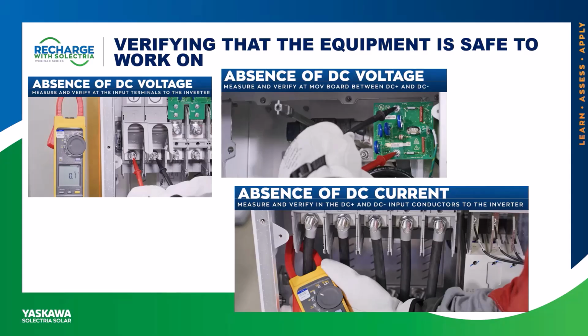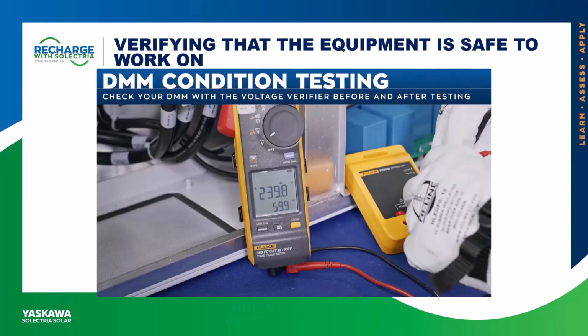So here's that little verifier I was talking about. Before we check our voltages, we want to make sure our meter actually works. This is a kind of cool little thing because it has a switch on the side where you can verify whether it's AC or DC voltage, which is neat. Again, check the meter, check the voltages, check the meter again. Always make sure that your meter's in good condition.